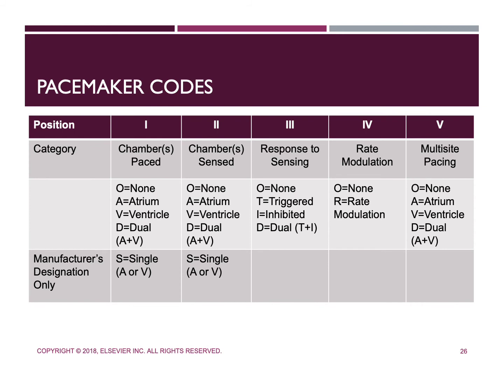Pacemaker codes are used to assist in identifying a pacemaker's programmable pacing, sensing, and response functions. The first letter of the code identifies the heart chamber or chambers paced. A pacemaker used to pace only a single chamber is represented by either an A for atrial or V for ventricle. A pacemaker capability for pacing both chambers is represented by a D, which means dual. The second letter identifies the chamber of the heart where patient-initiated electrical activity is sensed by the pacemaker. The third letter indicates how the pacemaker will respond when it senses patient-initiated electrical activity.